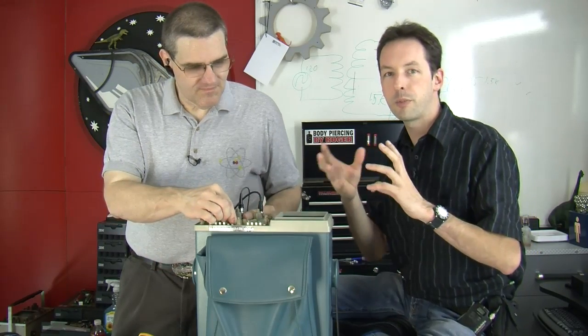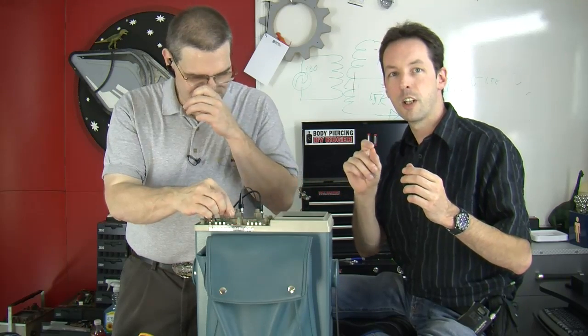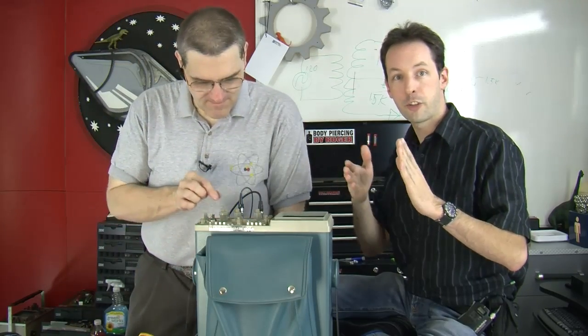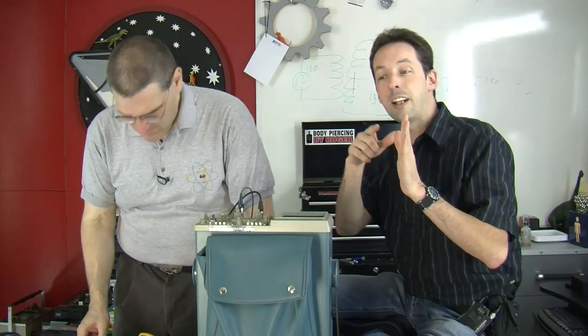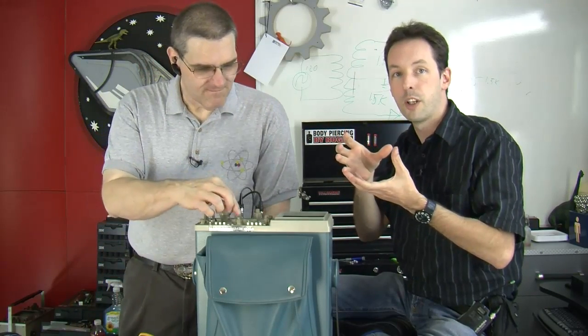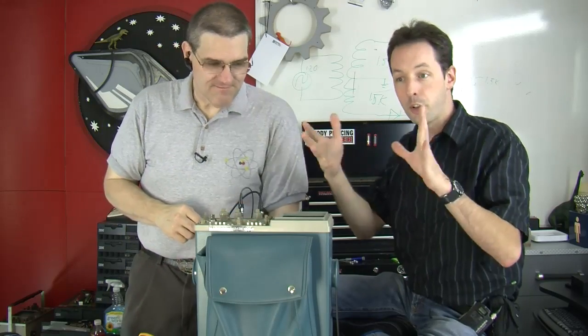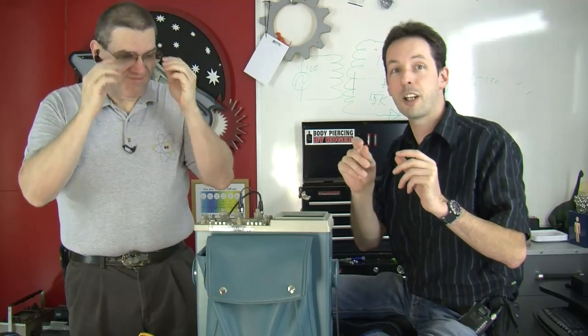It's really tiny, but it takes some serious amps to feed that little filament. So what they have is a transformer inside the big main X-ray transformer case, and this little transformer only outputs about a 3 volt difference. So the transformer is at 150,003 volts for this little tiny block transformer. When it feeds out to the tube, it sees 150,000 volts, but the little filament inside only sees 3 volts because it's floated up. So the whole transformer is floated up - the transformer itself is 150,000 volts relative to ground, but only 3 volts relative to its own power supply. That's how voltage can be relative. It all depends on where you measure from and to - you need 2 numbers for your voltage, or 2 references.